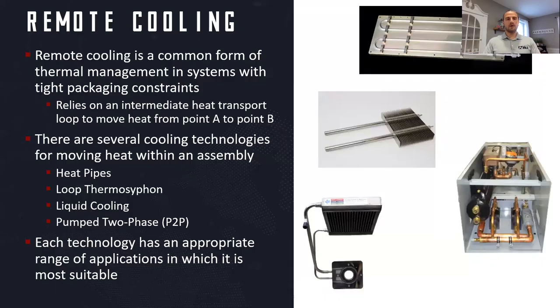Now we'll move on to remote cooling — one of the more common forms of thermal management where we move heat from the immediate area to some distance away, which could be inches or even tens of meters from your heat generating source. There are a number of technologies we use: heat pipes for transporting heat from one location to another, and other liquid-based solutions including a loop thermosyphon, standard liquid cooling, and what we call pumped two-phase. Each of these technologies has an appropriate range of applications in which it's most suitable.